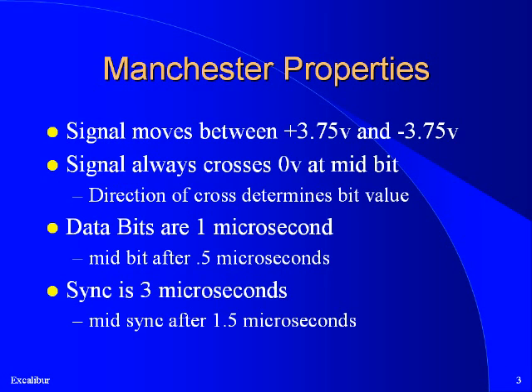Manchester encoding describes how the voltages flowing over the bus should be interpreted as ones and zeros by the devices connected to the bus. Each word begins with a sync signal, which looks different than a regular data bit. Devices use the sync to identify the beginning of a word. The signal moves up and down between plus 3.75 volts and minus 3.75 volts. In the middle of each sync or bit, the voltage moves from one extreme to the other, and the direction of this move determines the bit value. The voltage may also change values between bits, particularly if two bits of the same value are transmitted one after the other.